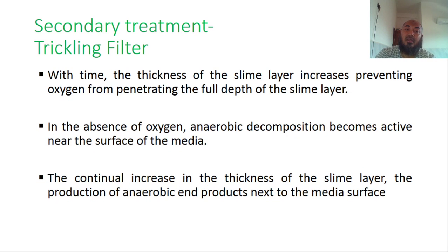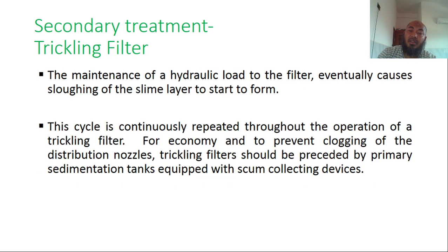With time, the slime layer thickens, preventing oxygen from penetrating the full depth of the slime layer. In the absence of oxygen, anaerobic decomposition becomes active near the media surface. With the continual increase in the thickness of the slime layer, anaerobic end products are produced next to the media surface.